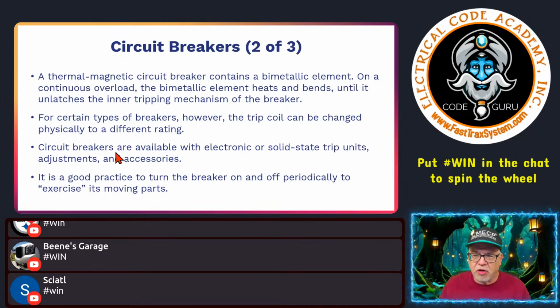Then you have circuit breakers available with electronic or solid state trip units, adjustments, and accessories. This is typically what you're going to see that activates the other components, like short circuit and ground fault protection, electronically.